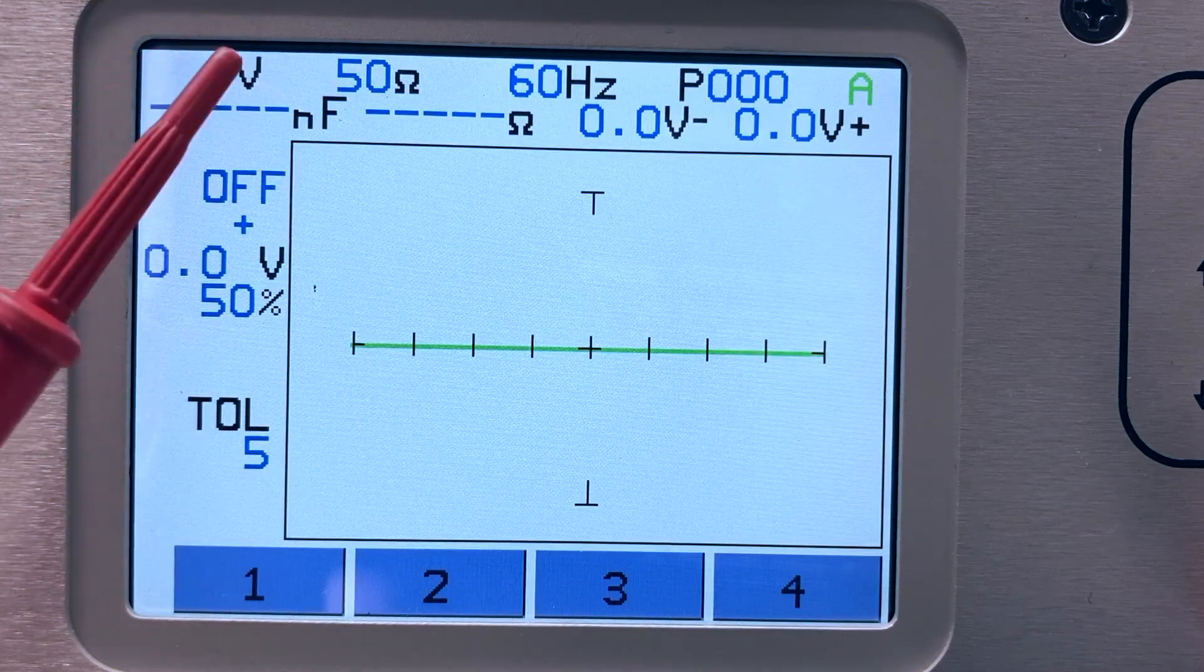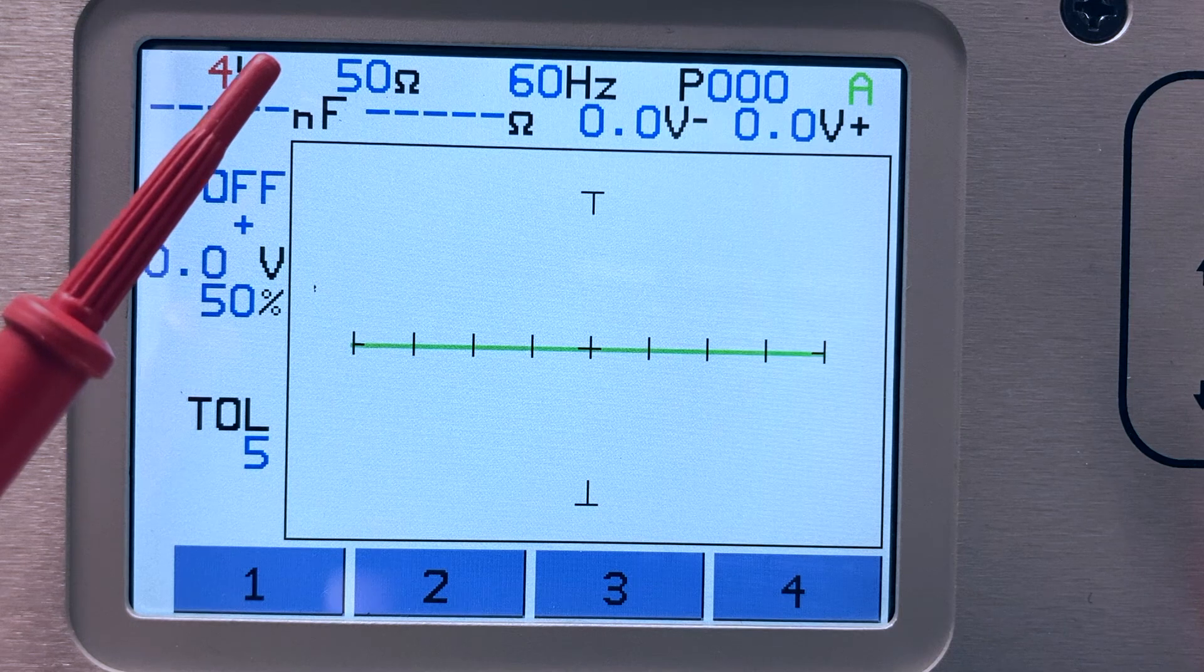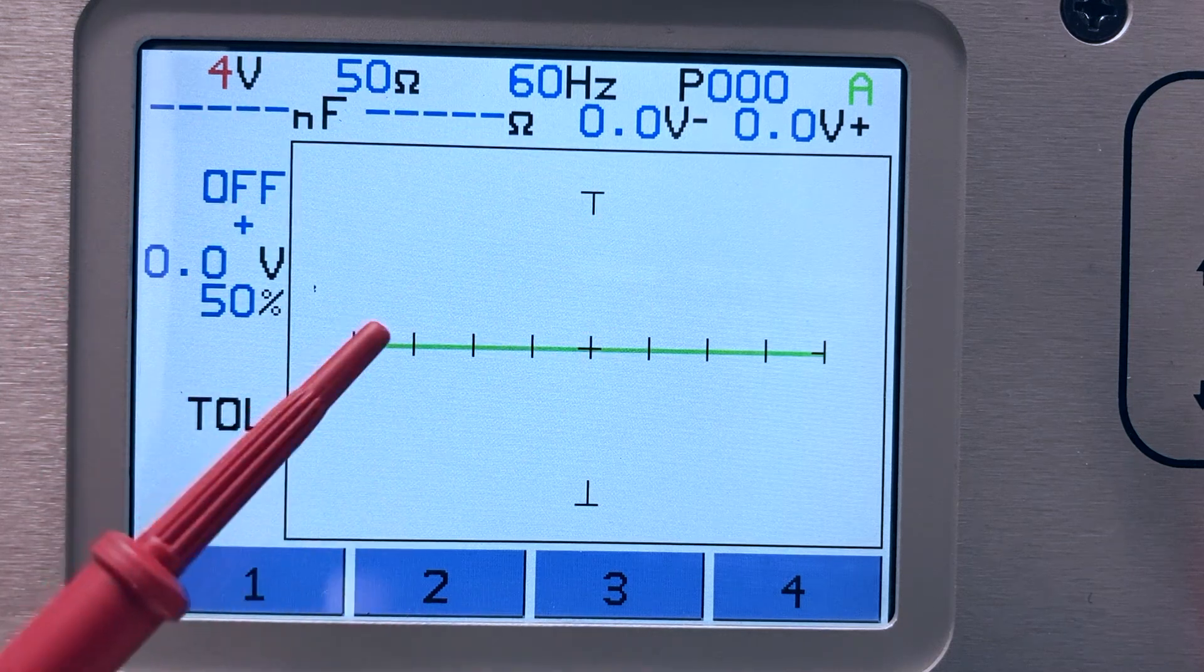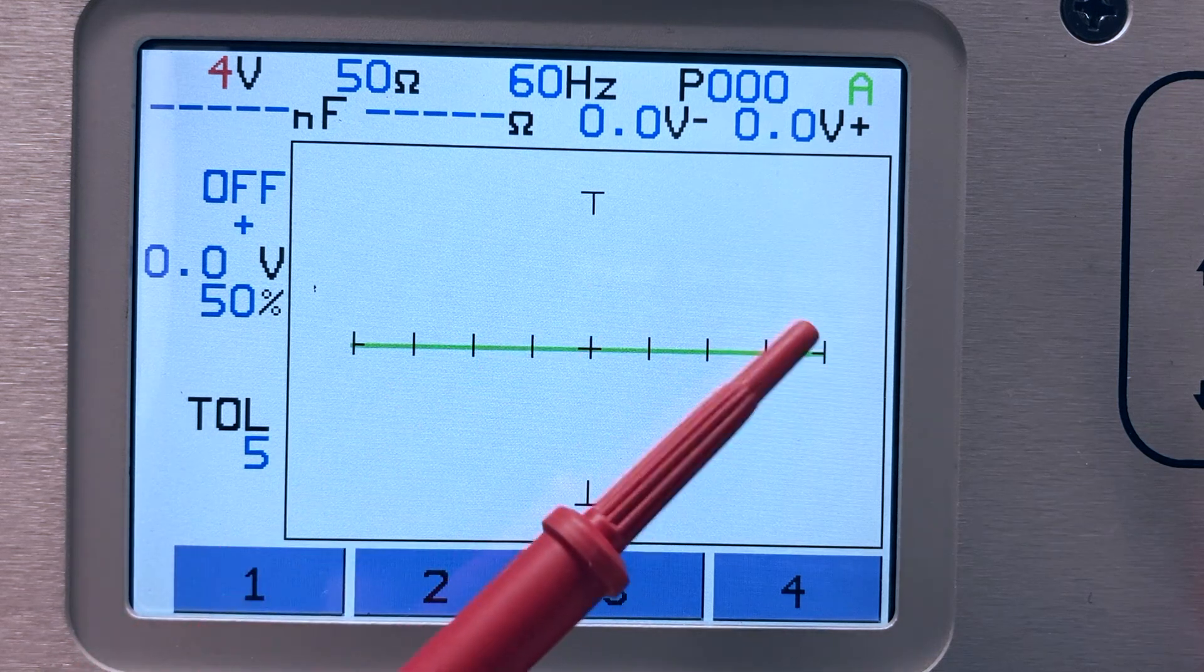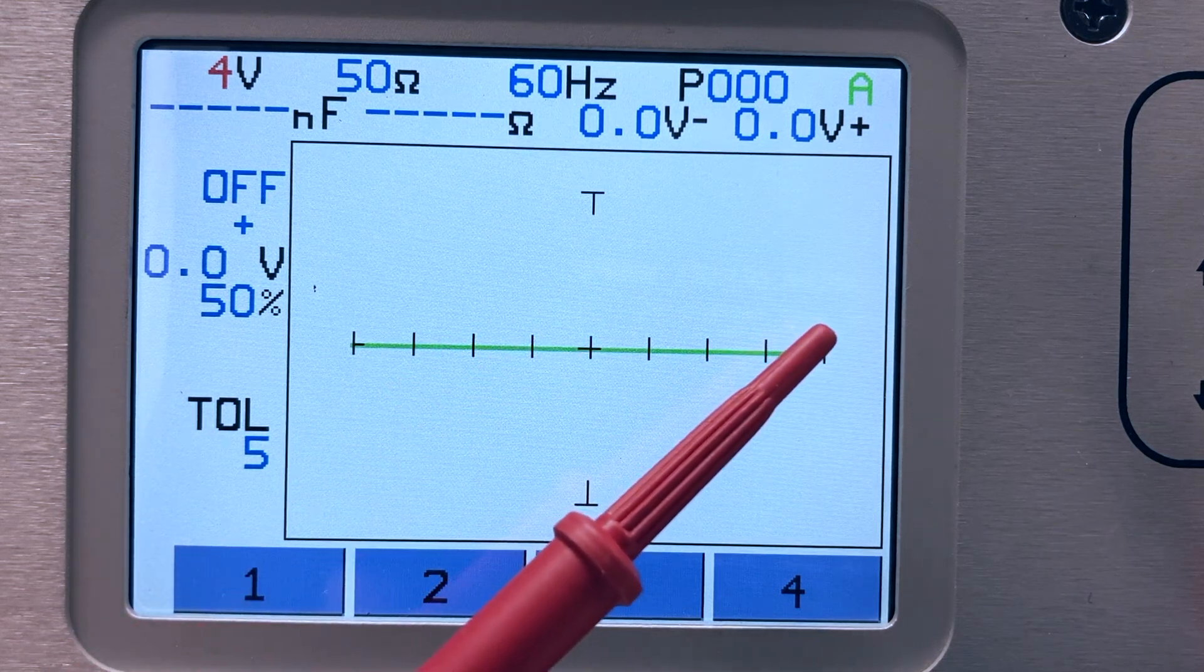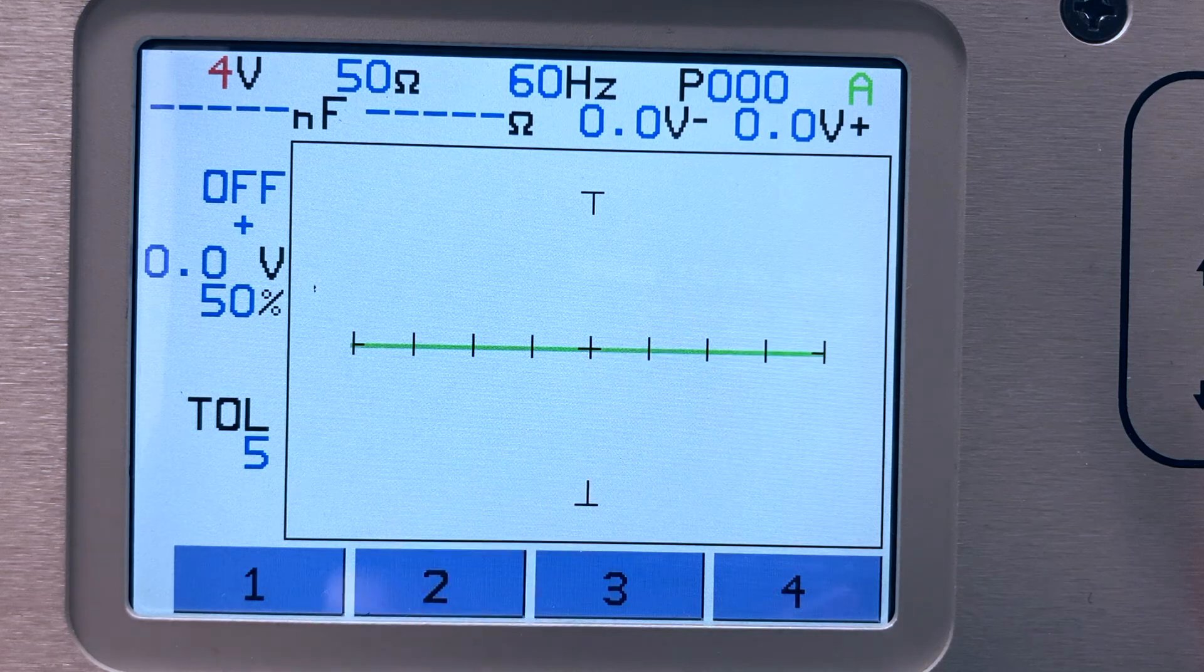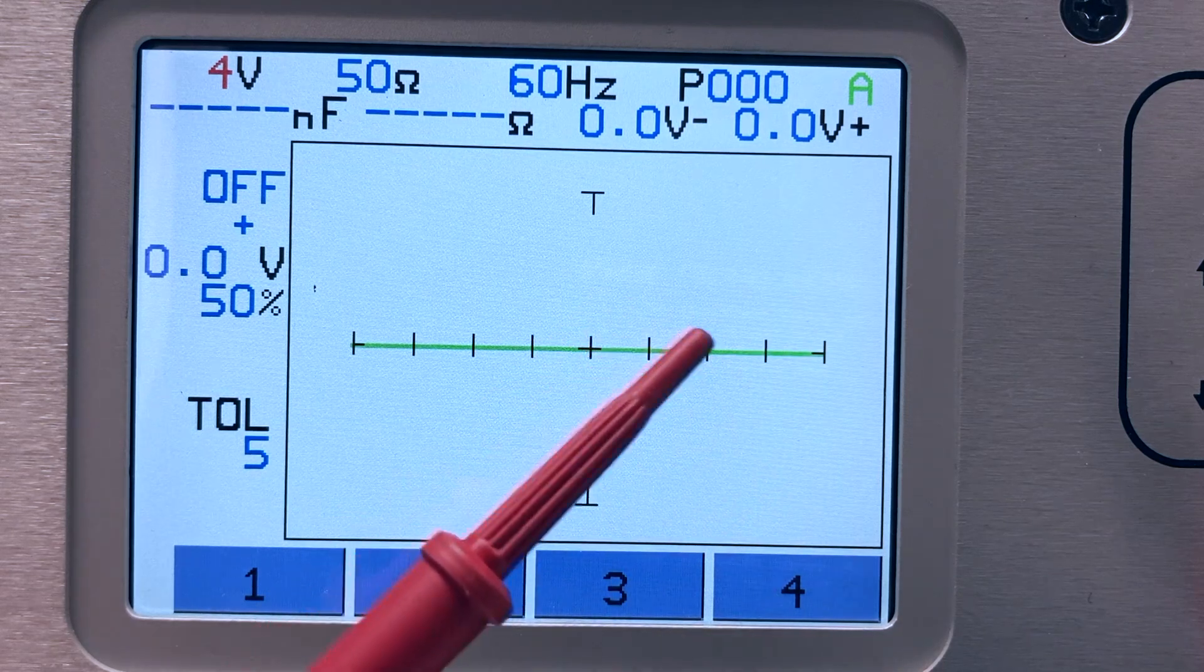As an example, if the tracker voltage is set to 4 volts, then the left end of the graticule is negative 4 volts and the right end is positive 4 volts. Since each side of the graticule is divided into four divisions, this means that each division is worth 1 volt.